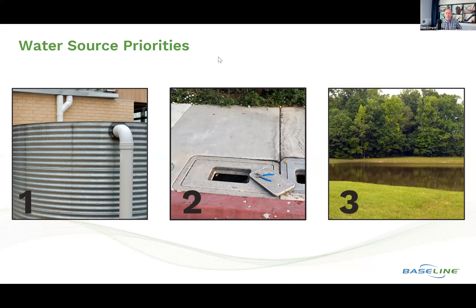Here's how I programmed this site: the tank — most important — is set to priority two. The domestic meter is the middle option, set to priority four. The pond is set to priority six. I used two, four, and six rather than one, two, three to leave room in between, giving me the ability to move them around and change the priority later without having to renumber everything.